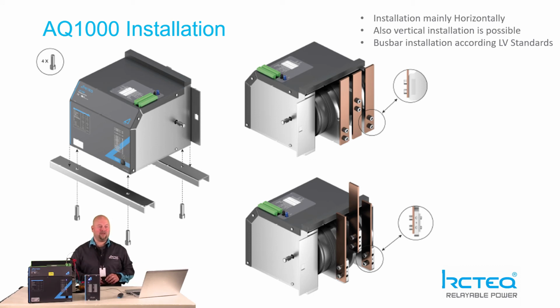Installations are mainly horizontal, but this unit can also be installed vertically, for example behind doors which are narrower in space. And busbar installation according to low voltage standards and local standards, whatever is used in your country. Busbars can be mounted in many possible directions, and here are 2 examples of how to do the correct bolting to the system.